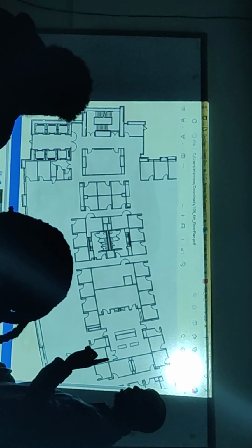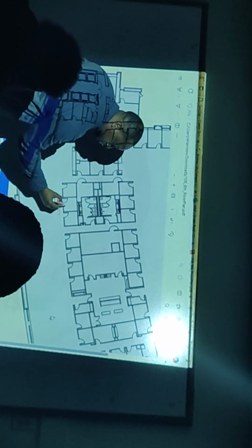But the typical standard is if I've got 3 clustered rooms like this, I can do 1 thermostat and 1 VAV. So theoretically, I will put a VAV right here outside the room. I'm just going to put a V. And I'll put a thermostat probably right here in this person's room. That symbol right there, the T with the circle, is a symbol for a thermostat. And then I've got my VAV, right?